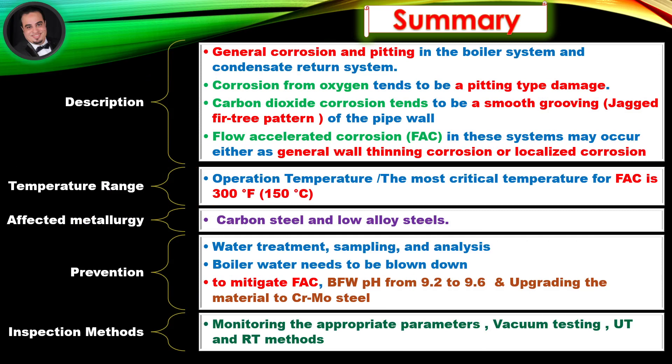Summary — Description. General corrosion and pitting in the boiler system and condensate return system. Corrosion from oxygen tends to be a pitting type damage. Carbon dioxide corrosion tends to be a smooth grooving, jagged fir tree pattern of the pipe wall. Flow accelerated corrosion in these systems may occur either as general wall thinning corrosion or localized corrosion.